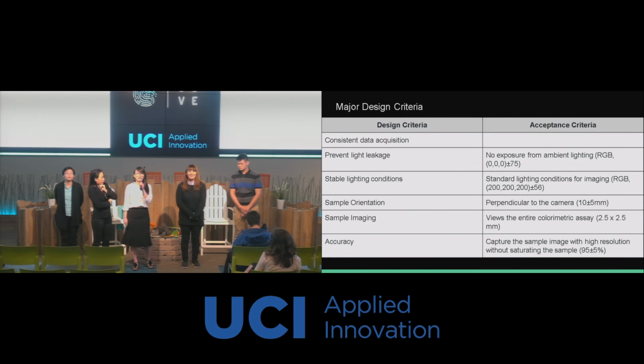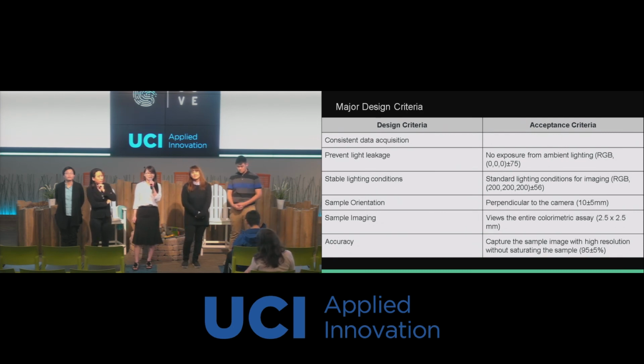So our major design criteria is to keep the data acquisition consistent, which means preventing leakage. There should be no other light besides the LED, and the light should be stable, which means we should avoid LED failure during the process. The camera should be able to view the entire colorimetric assay and capture the sample without saturating it. And the sample has to be perpendicular to the camera.